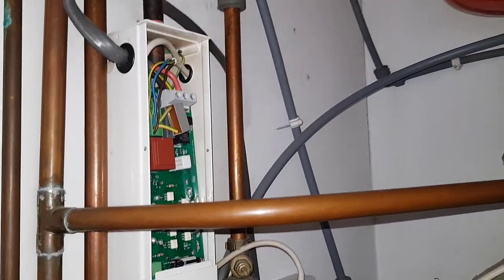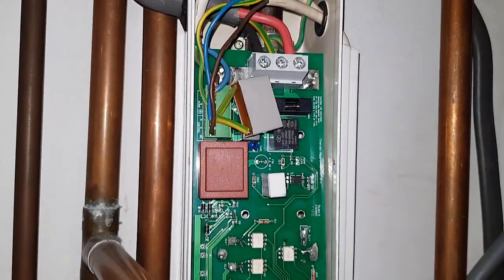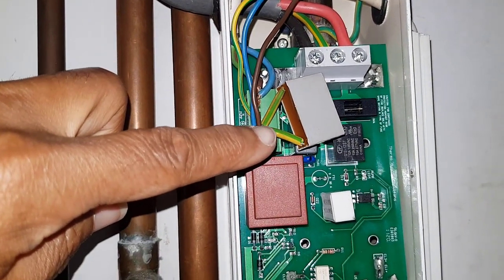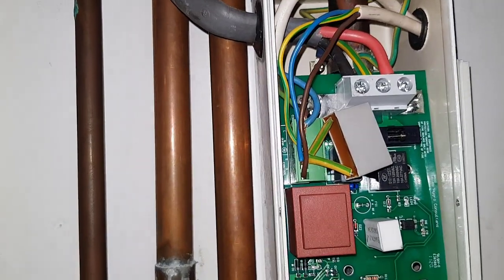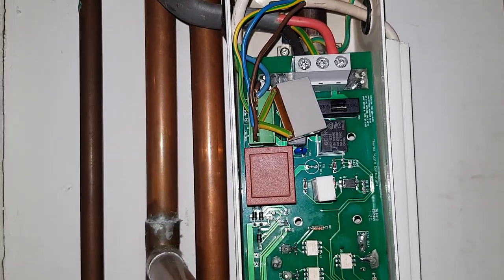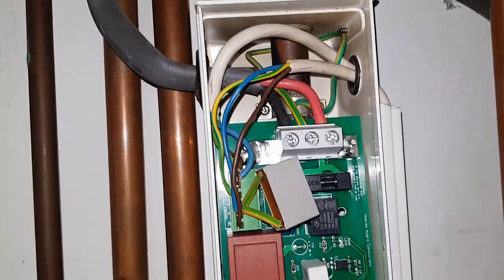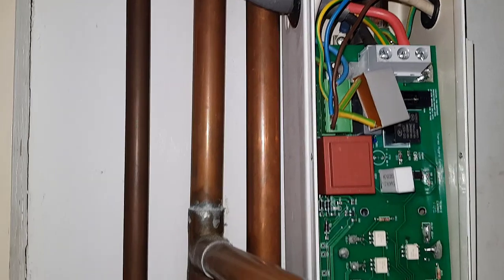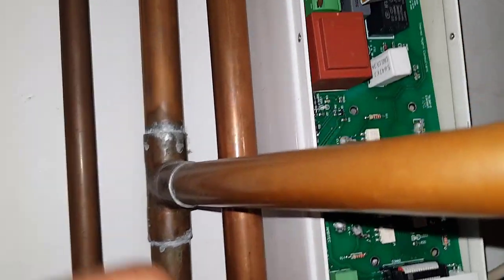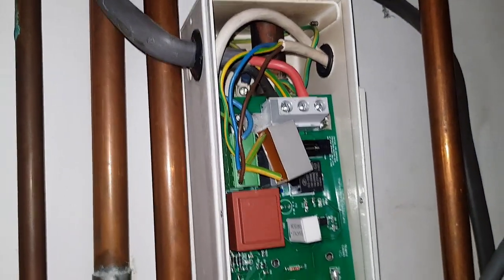We're going to look at the boiler more closely. Looking at this PCB, there's something here which isn't really necessary — I've never seen one like that before. Also, the PCB doesn't look secure; it's not fixed properly. It looks a bit cockeyed — very close to this part here and tapering away, leaning back. It hasn't been installed very well.